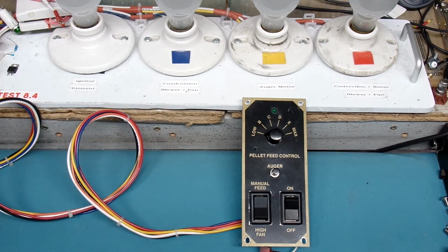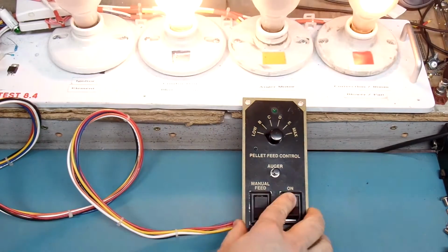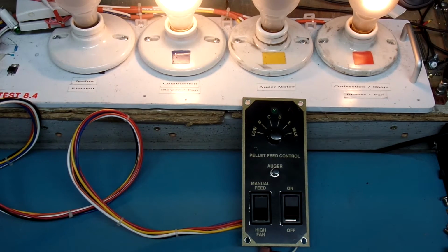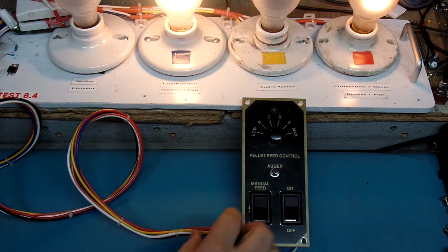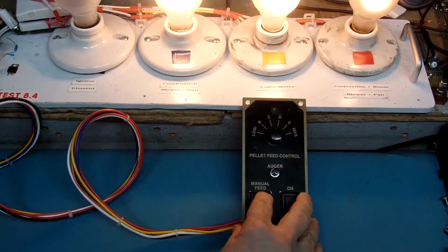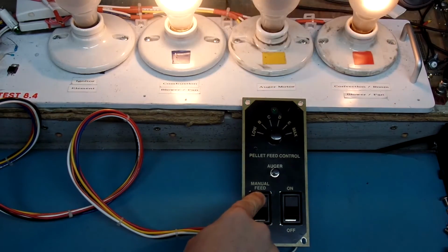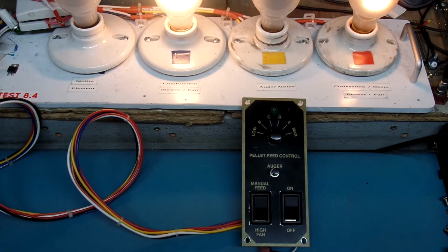So I'll go ahead and turn it on, and when I do that I expect the combustion fan to come on and the convection or room fan. The couple things that I can do now, because I'm in manual mode, so my green light at the top is not on, is a manual feed, which is the momentary switch. And we see that pressing that in a momentary fashion causes the auger motor to receive voltage. So that means the auger motor would spin and drive pellets into the fire pot.